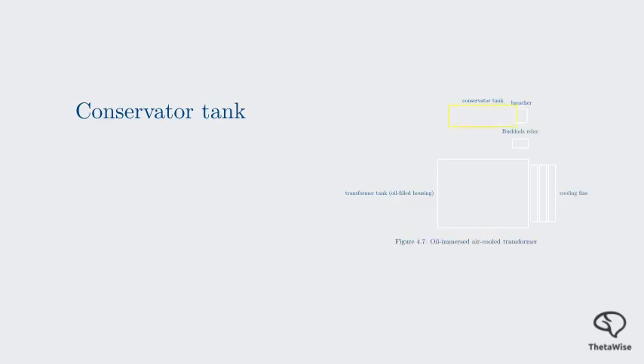Beyond cooling, transformers have several vital accessory components that ensure their safe and efficient operation. Let's examine the first, the conservator tank. As we just discussed, the transformer oil heats and expands. If the tank were completely sealed, this expansion would create immense pressure, which could damage or even explode the tank. To prevent this, a smaller conservator tank is mounted above the transformer's main tank. Its function is to provide extra volume to accommodate the expansion of the oil.